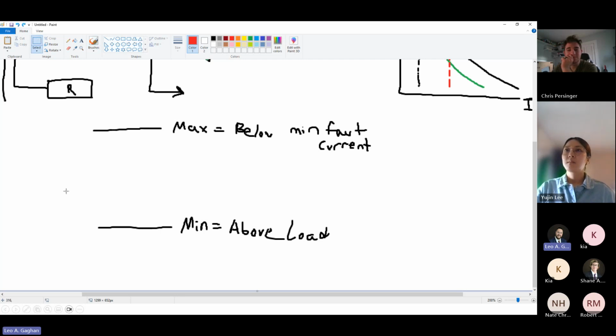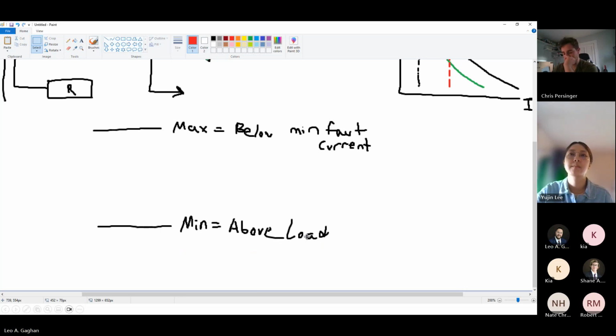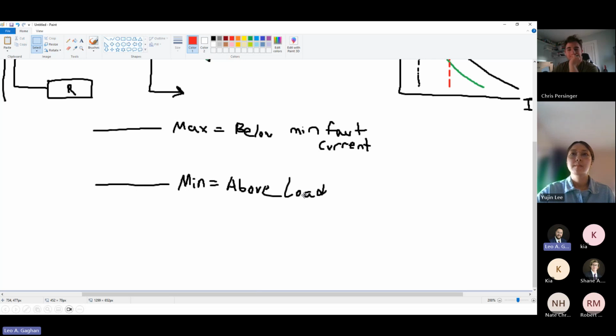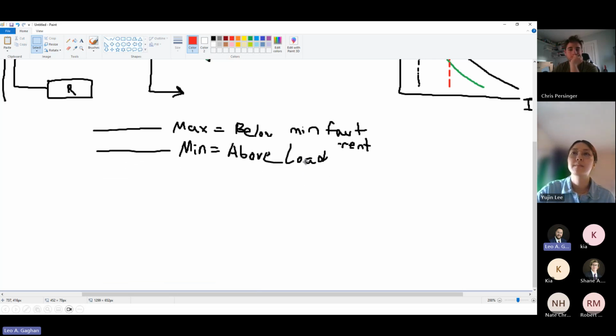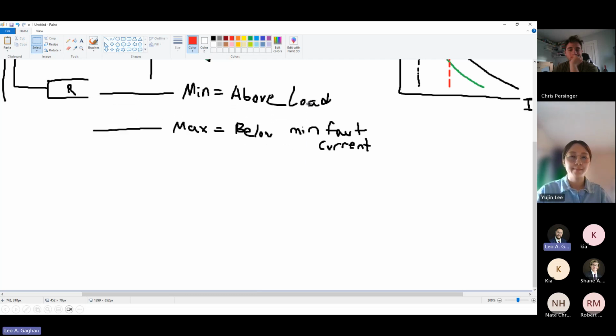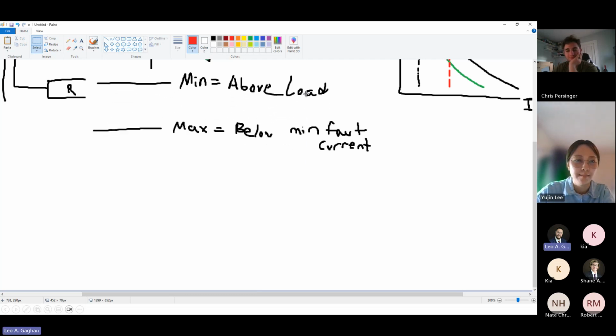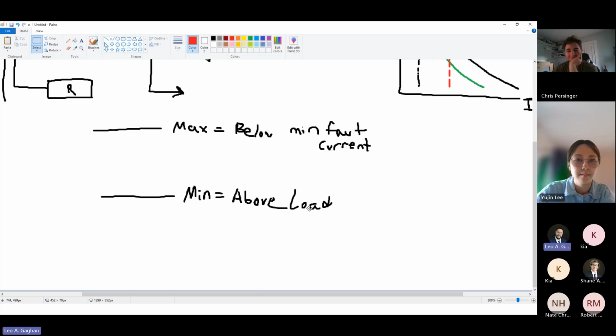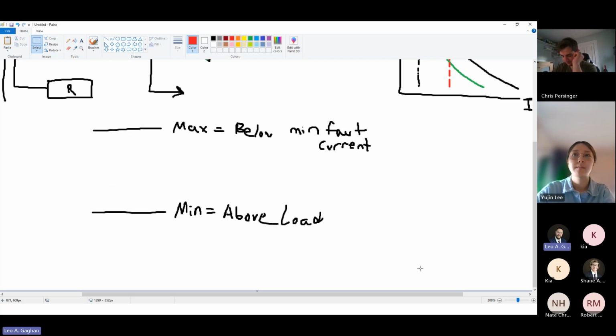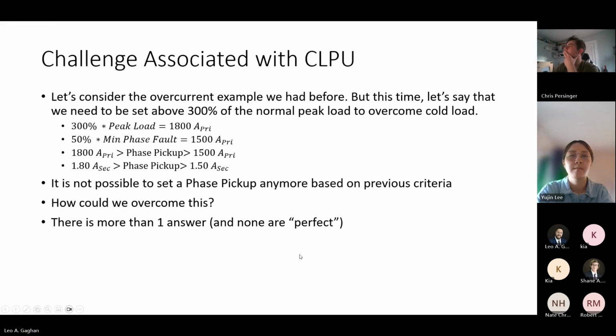Challenge with cold load pickup, we still need to be set above that cold load. The challenge with it is now, okay, our margin, our acceptable window is getting smaller. It's getting smaller. Oh no, what do we do now? Our minimum acceptable criteria and our maximum have crossed, and we don't have anything that's acceptable. All right, that's a serious problem. What do you do in that situation? That's what we want to talk about with the cold load pickup. So how can we overcome that? There's more than one answer here. Does anyone have any ideas?